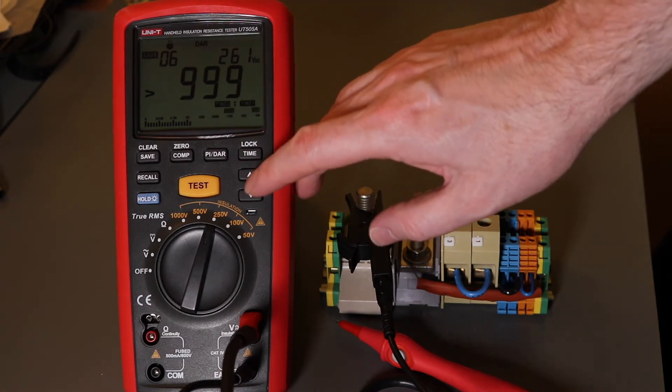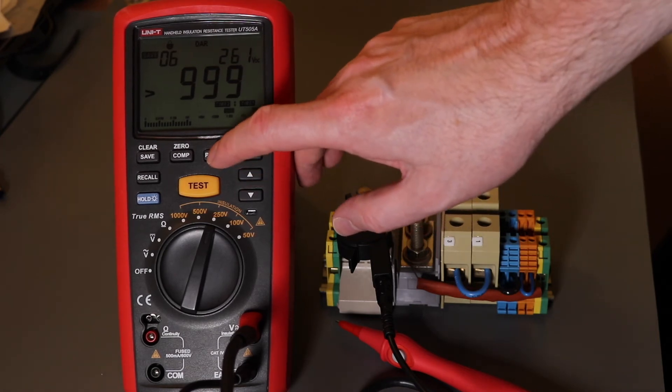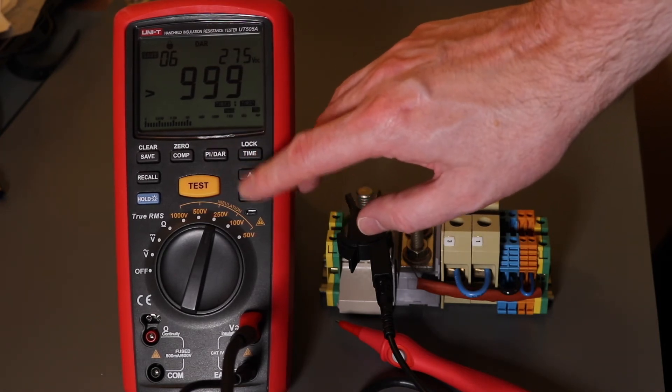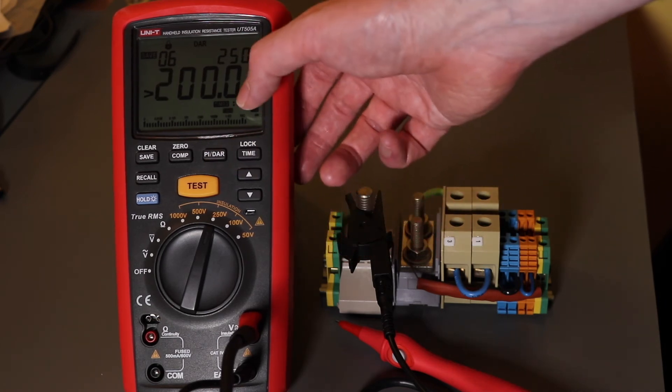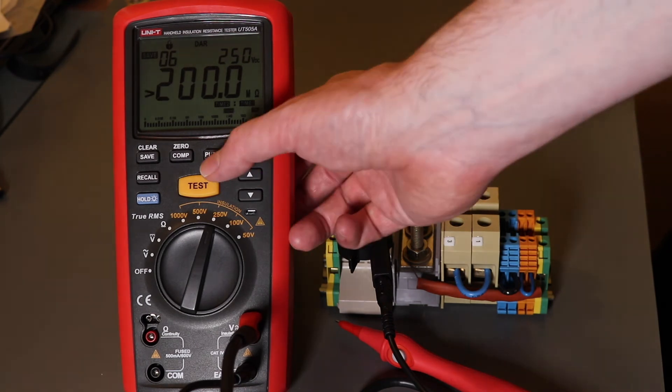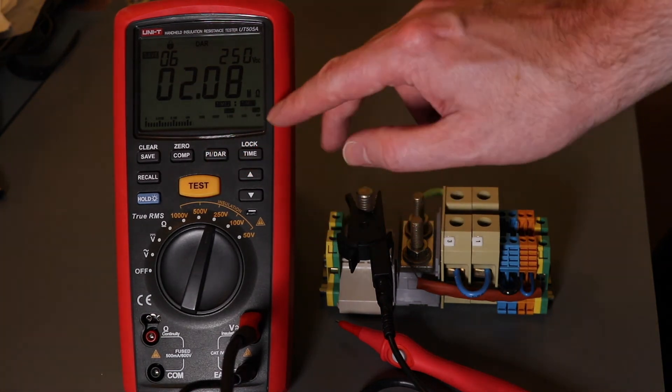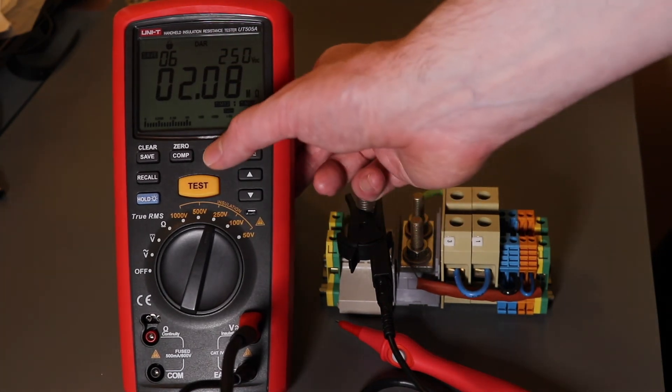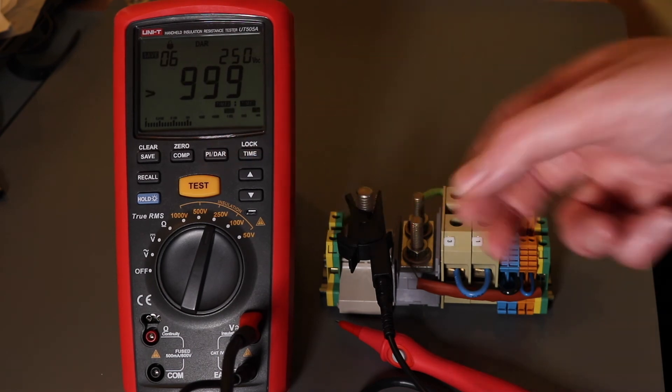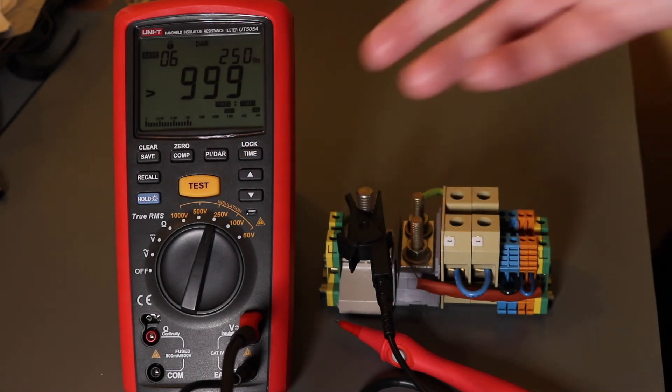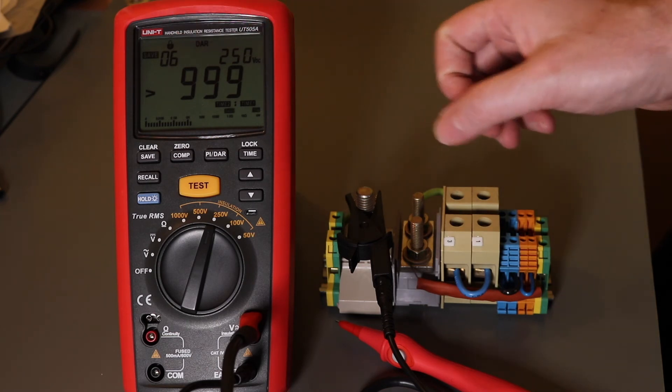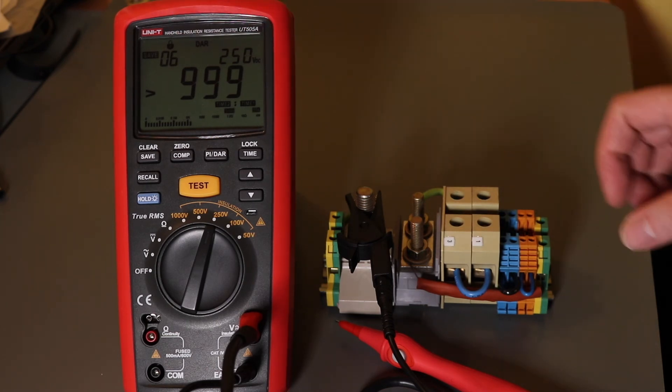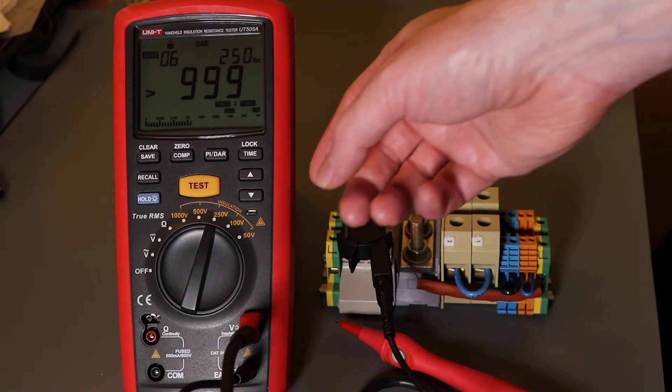Anyway, as I was saying, once you've... So the one minute reading was 200Mohm. 15 second reading was 2.08Mohm. And obviously it can't record the ratio value there. But it would have displayed that ratio value when you've got a proper reading at the one minute time.